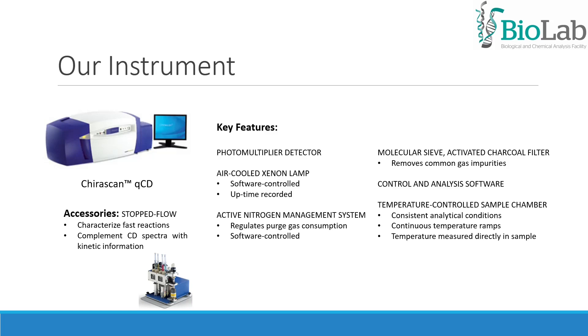At the Biolab, we have the Chirascan™ qCD by Applied Photophysics. This device has the features and accessories required for acquisition of high-quality data, such as a temperature control sample chamber that allows for consistent analytical conditions and continuous temperature ramps. We also have the Stop-Flow accessory, which allows us to characterize fast reactions and complement CD spectra with kinetic information.